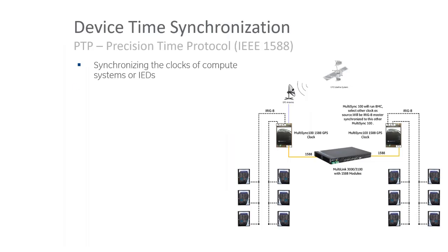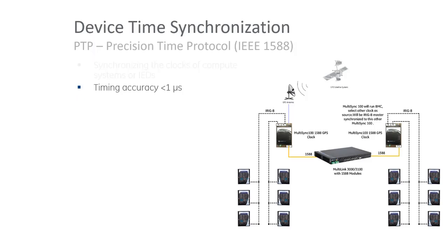Ethernet also enables time synchronization. Instead of IRIG-B, which requires a dedicated BNC cable, we can use IEEE 1588 — commonly referred to as PTP, Precision Time Protocol — to synchronize the network. The accuracy is as good as or better than IRIG-B, with less than one microsecond accuracy, making it suitable for the most demanding time synchronization applications.